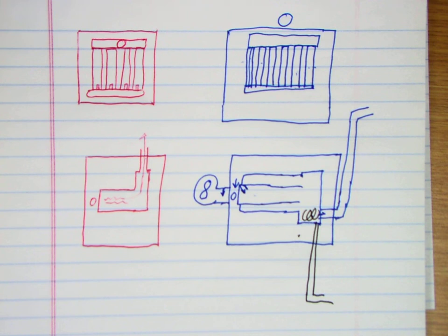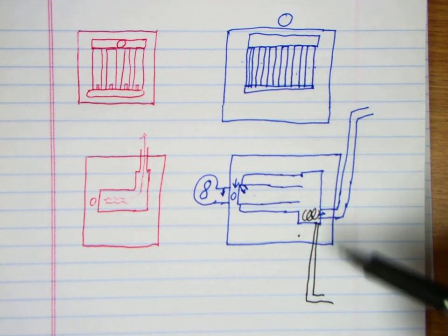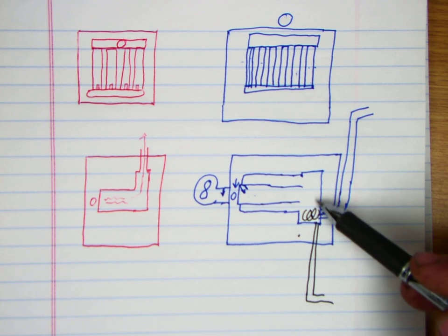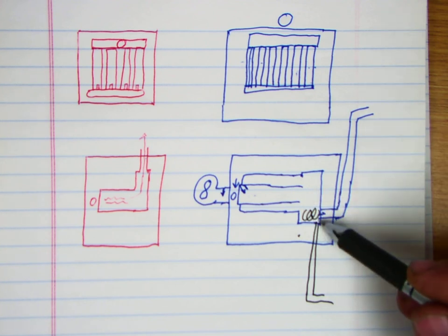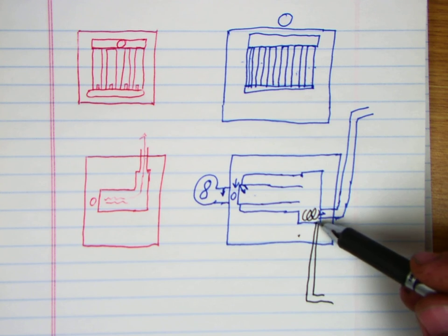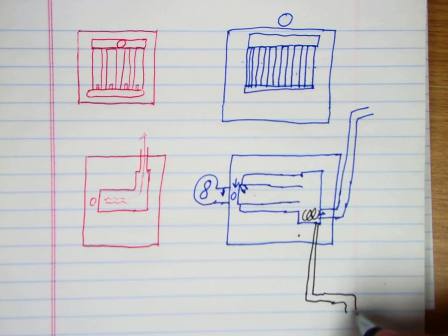There's always some water vapor both in the air or in the materials that we're burning, and we've got to get rid of that. So they put a drain on a high efficiency furnace because the water actually condenses. That's where the term high efficiency or condensing furnace comes in. That water condenses, and then we have to drain that out and put it into a floor drain.